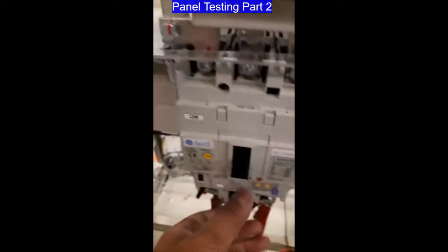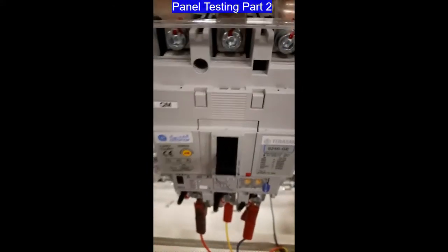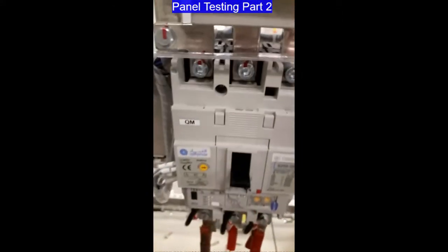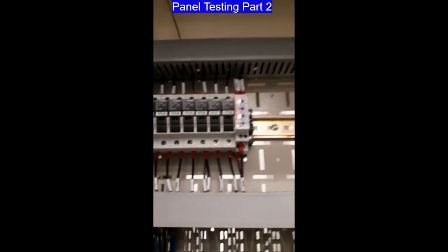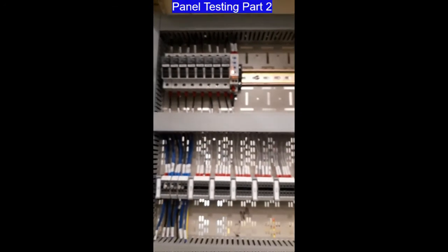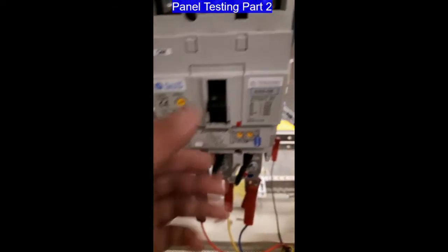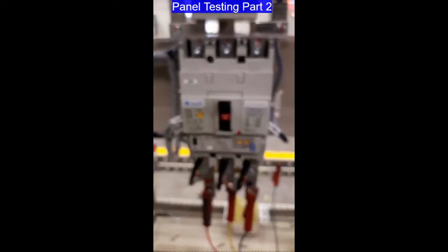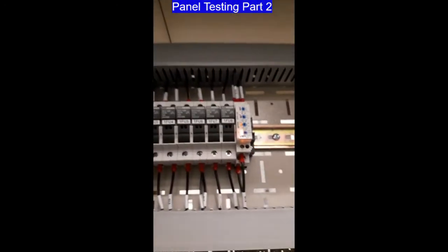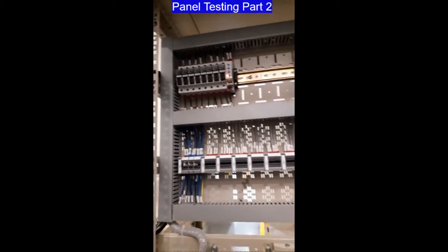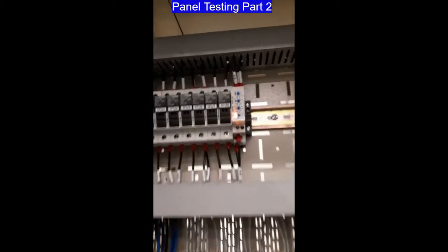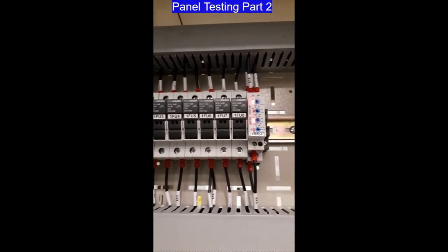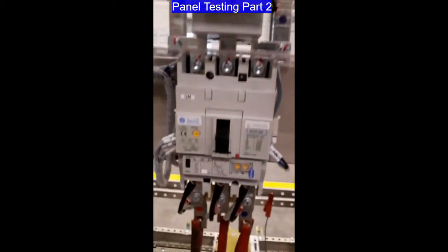Once you are in trip status, you cannot reset the breaker because the failure is still there. If you try to switch it on, you cannot unless you reset by returning to normal voltage. Okay, now it's normal, so again we switch on the breaker. It's in on condition now, and the VMR is healthy. In case there is a failure again, that's the function of our voltage monitoring relay. We'll get the signal and it will trip the breaker.